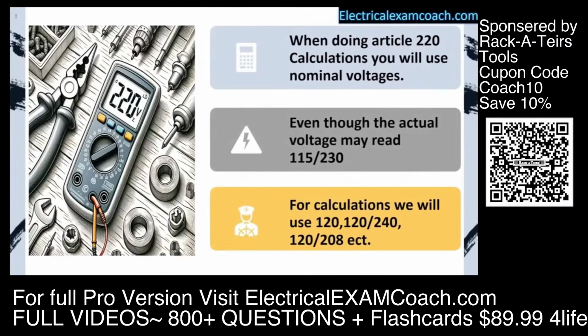When doing Article 220 load calculations, we're going to be using nominal voltages. Although our actual meter reading might be 115 or 230, for our calculations, we're going to be using nominal system voltages like 120, 120/240, 120/208. It makes it a lot easier to do these calculations, not having to guess or wonder what the actual voltage readings might be.